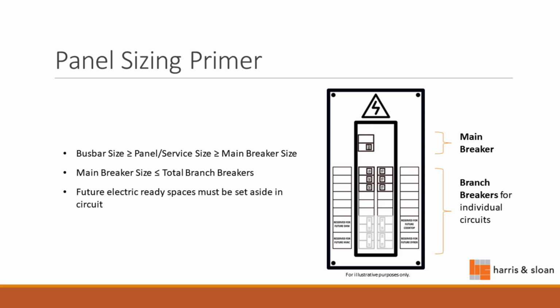Now if we look at the individual branch breakers here and add up their sizes, we'd find they actually add up to something like 300 or even 400 amps, which is obviously bigger than the main breaker. We're able to do that because we know nobody's going to turn on all the lights in their house, plug in all their outlets at maximum load, while also running their dryer, heater, dishwasher, and everything else at the same time.